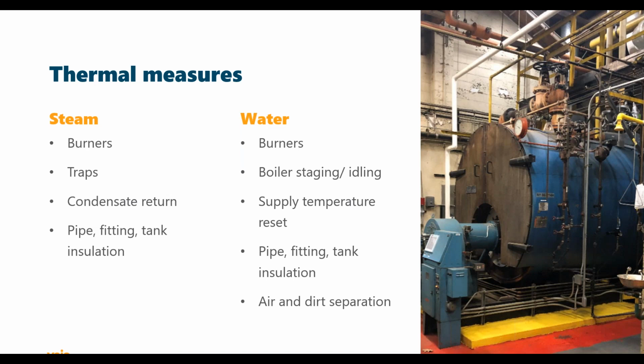Condensate return is really visible. If there's condensate dumping onto the floor in the mechanical room, there's an opportunity. Anytime a customer isn't returning condensate, that's expensive. Heating water from 55 degrees to 220 takes a lot more energy than heating it from 170 to 220 or higher, depending on their steam pressure.